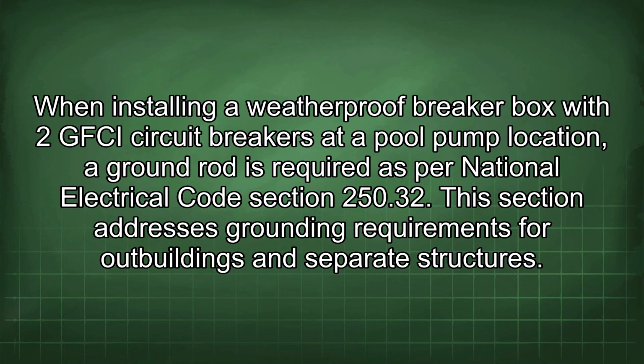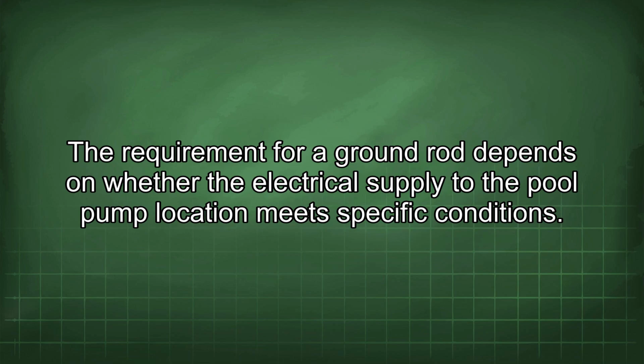When installing a weatherproof breaker box with two GFCI circuit breakers at a pool pump location, a ground rod is required as per National Electrical Code section 250.32. This section addresses grounding requirements for outbuildings and separate structures. The requirement for a ground rod depends on whether the electrical supply to the pool pump location meets specific conditions.